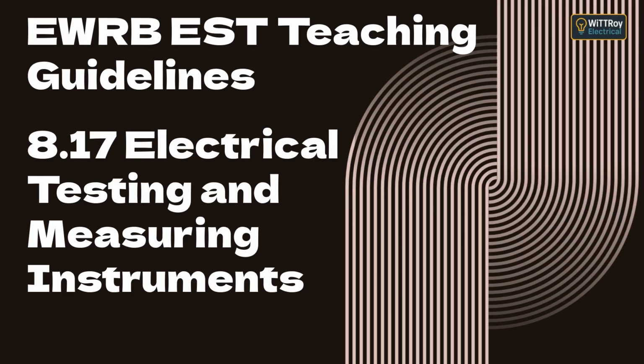2. Insulation resistance test. Purpose: to check for leakage between active, neutral, and earth conductors. Method: use a 500-volt insulation tester with the circuit isolated. Expected result: at least 1 megohm, with readings above 10 megohms preferred for new wiring.